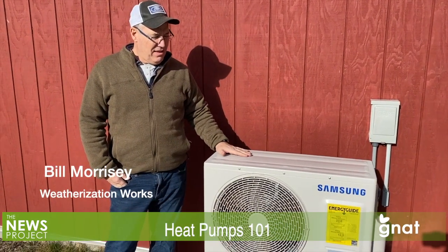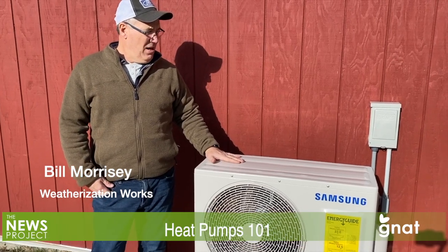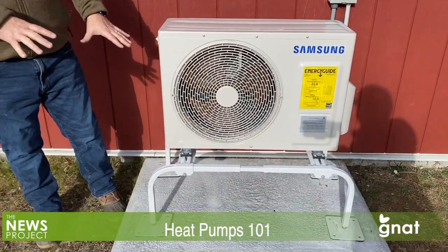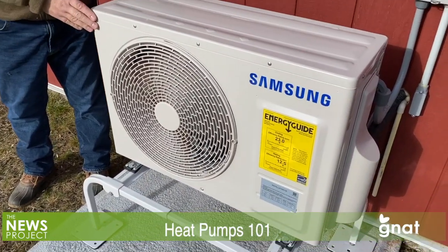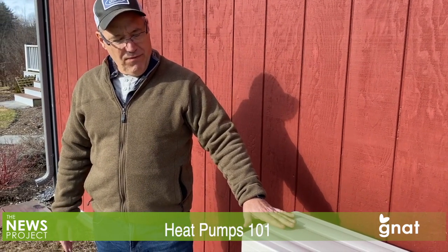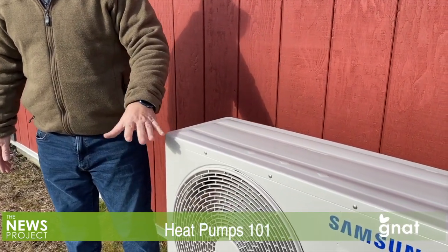Andrew, I like that this is a good example of a ground mounted unit. So this whole system sits on a ground mount where the feet are independently adjustable — so over time, if this unit for some reason becomes out of level, you can independently level it. It's a good idea that the outdoor units stay relatively level. During the heating season, ice will form on the coil, and it needs to get away from the outdoor unit.